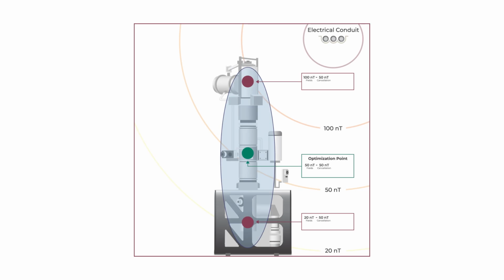And so the result is, if we've optimized the field cancellation system for the center, we have under canceled by 50 nanotesla at the top and over canceled by 30 nanotesla at the bottom. And if the spec is 20 nanotesla peak to peak, we basically are out of spec at both the source and the detector level, which is problematic.